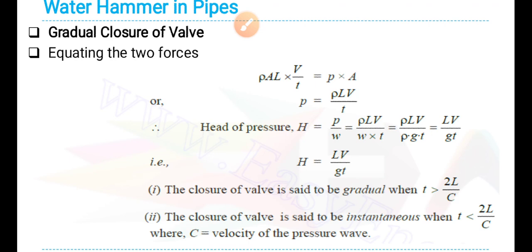If it is gradual, T must be greater than 2L by C. In order to say it is instantaneous or sudden or rapid, T should be less than 2L by C, where C is velocity of the pressure wave as I already said.